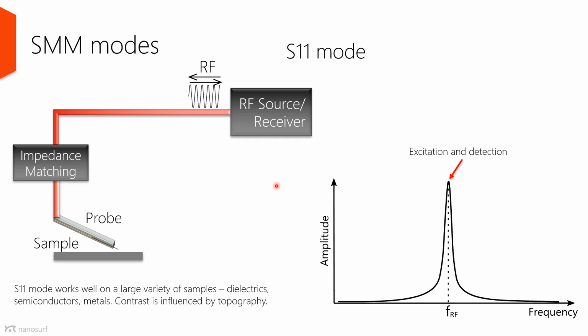Here, I would like to talk a bit about two different SMM modes of measurement. The basic SMM mode, as we already know it, is the S11 measurement. In this case, the source and the detector are working on the same frequency, a high frequency of several gigahertz. And the spectrum is rather simple. It's just one tone and there is nothing else except this tone. This mode works well on a large range of samples: dielectrics, semiconductors, semi-metals, but it does suffer from the topography crosstalk.